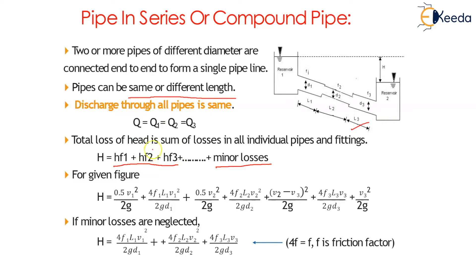For the given figure, the total head loss is: 0.5·V1²/2g (entry loss) + 4F1·L1·V1²/(2g·D1) (friction in pipe 1) + 0.5·V2²/2g (sudden contraction) + 4F2·L2·V2²/(2g·D2) (friction in pipe 2) + (V2−V3)²/2g (sudden expansion) + 4F3·L3·V3²/(2g·D3) (friction in pipe 3) + V3²/2g (exit loss).